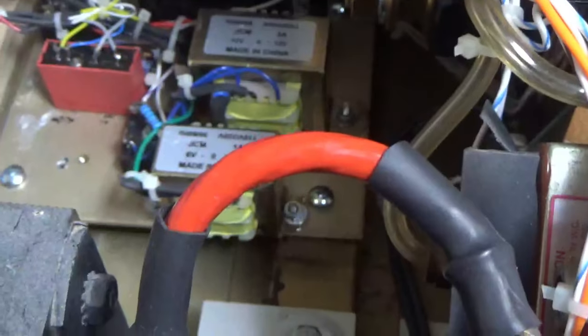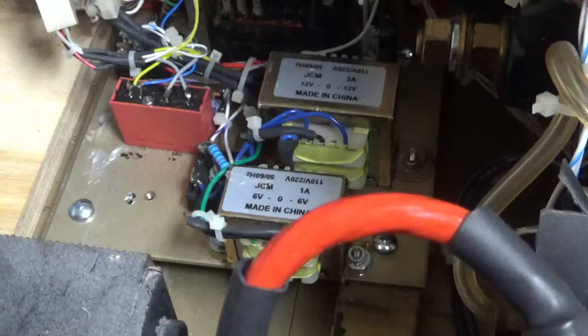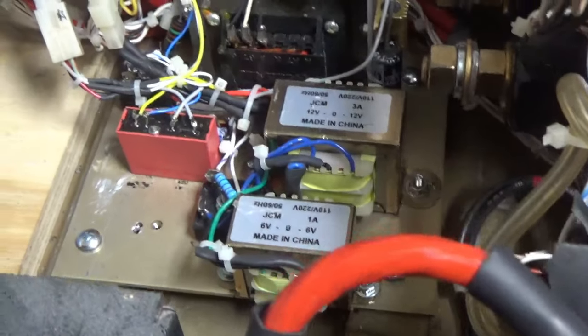Some more interlocks: if this assembly is removed, it shuts it down. I have a thermal switch, so if the intake temp were to rise above a certain amount, it opens the key line.